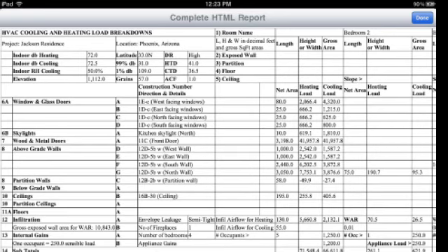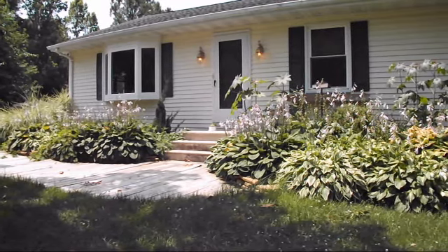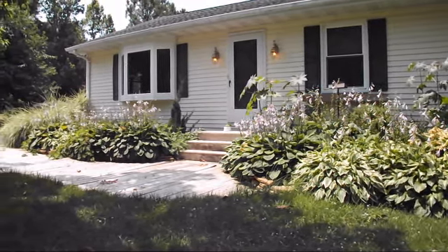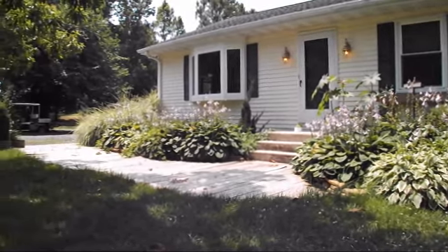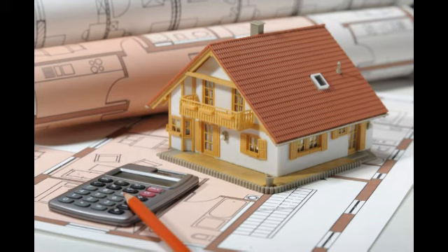This calculation is the tool used to determine what the actual heating and cooling load is for a specific house. This calculation takes into account the specifics of your home's envelope. A home's envelope is the outer shell, the part of your home that is responsible for keeping you hot or cool. It is a measurement of your home's insulation value and the heat gain or loss and the infiltration rate of your home. This is step one of the process, and if mistakes are made here, they will amplify later into poor performance of your system.